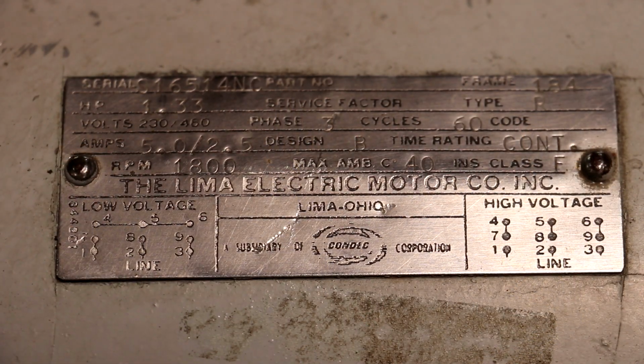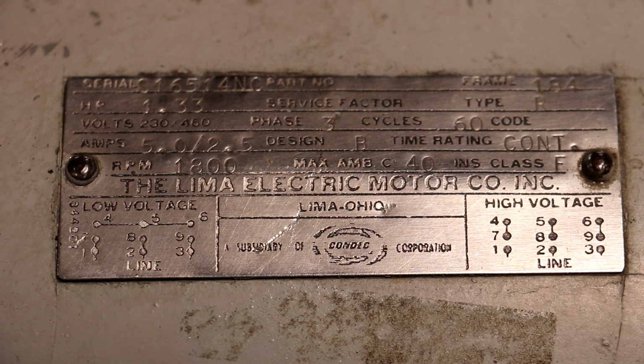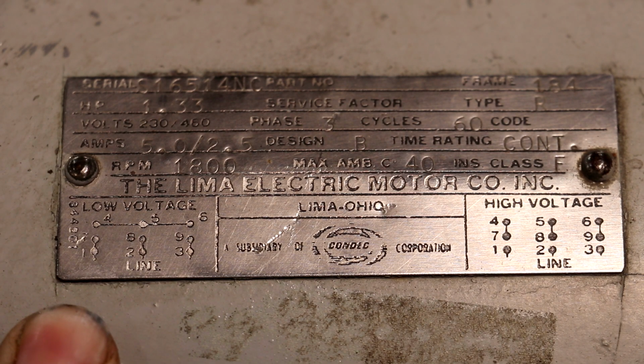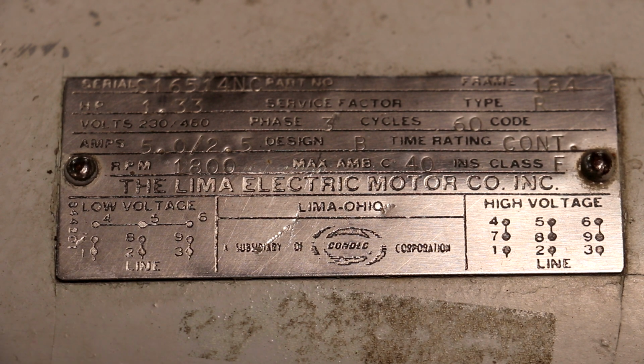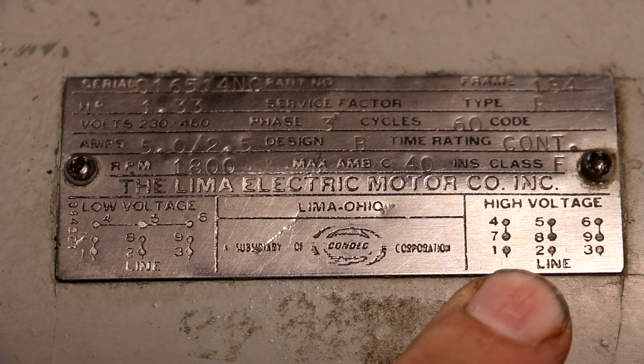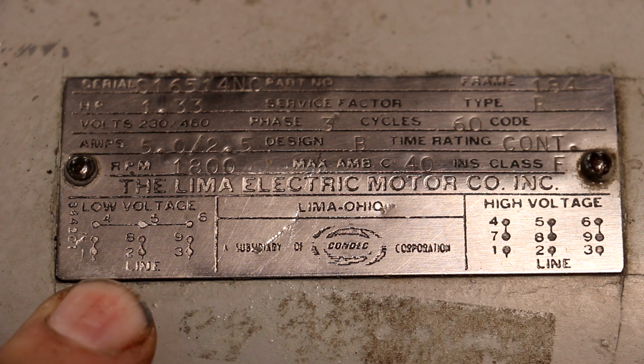How can you tell if your motor is a dual voltage motor? You look on the motor plate and it's going to show you the options here. Notice up here we got low voltage and high voltage, and there's a wiring diagram for the wires that come out of the motor. Now typically on a three-phase motor you're going to have 9 wires that come out of the motor. Basically 3 wires on each of the different inputs, and depending on how you configure those, as you can see how you tie those together in the motor, or in the pecker head down here where all the wires come out, that determines on what voltage you're running. So I'm sure that we got it set up on high voltage right now, and basically I need to pull those out. Those wires should be numbered 1, 2, 3, 4, 5, 6, 7, 8, 9, and we'll just have to change the way they're tied together in there and go from there.